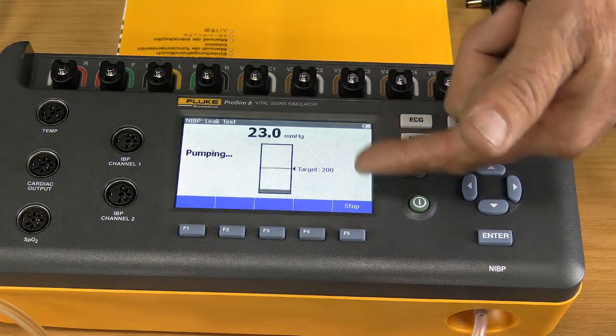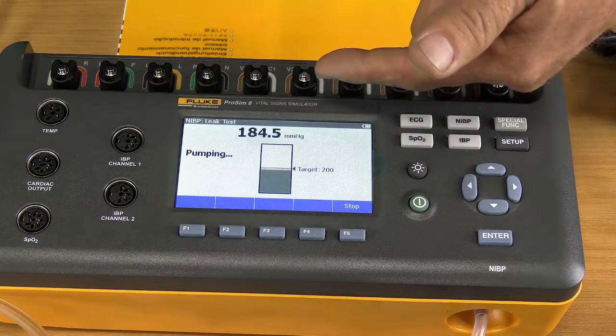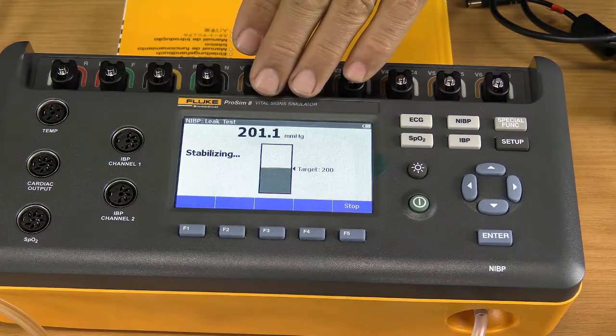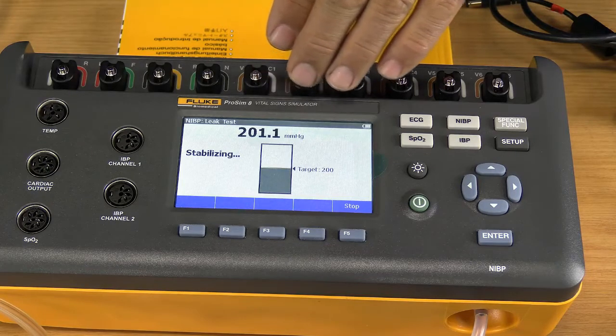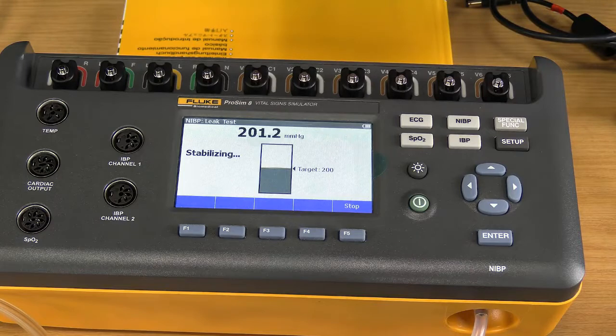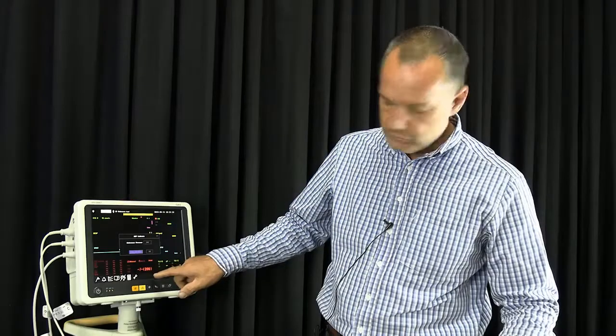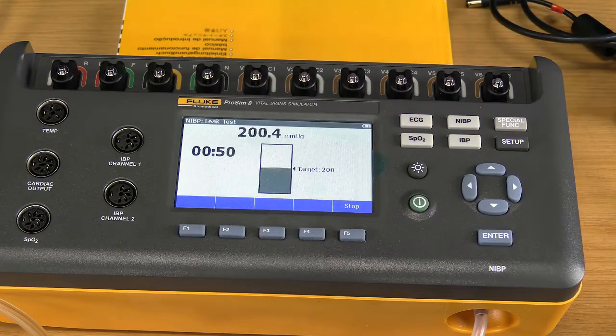Now you can hear and you can see how the machine is applying the pressure to my monitor. I can see on my monitor here where the pressure is. Then there's a stabilizing time in which the machine waits for the pressure to stabilize. So you know everything sets out, all the tubes expand, all the valves got closed properly. It's still stabilizing. You can see our pressures are very close, 201, 201. And then you can see the counter starts counting. So now the pump has stopped and we've closed the valves. And we're looking at the pressure drop over a 1 minute period.